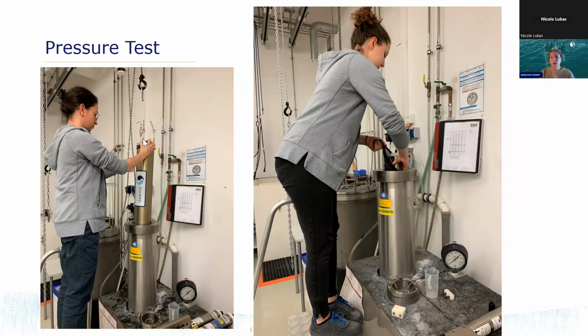and we do 2 sets of tests. One is at low pressure. Low pressure is actually really good for finding leaks. So if there is a problem with the O-ring, if something has been misassembled, a low pressure test is going to reveal that. Then we do a high pressure test. And the high pressure test is, again, to really check the integrity of the materials and anything that we've repaired, just to make sure you can go all the way to the depth that your instrument's rated at, and you're not going to be having any problems.